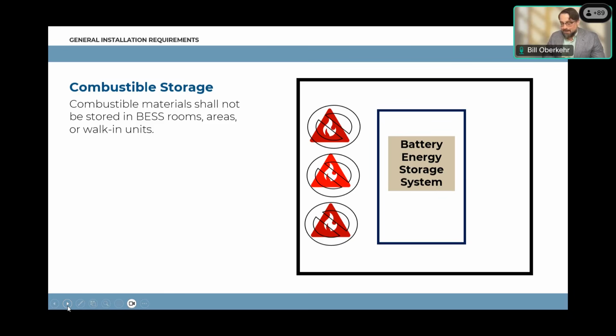And as Paul said, this is not a fire elimination code, it is a fire prevention code. To that end, the fire code requires that there be no combustible material within 3 feet of cabinets containing energy storage systems. This is critical, and it's one that unfortunately gets overlooked. It's one that NYSERDA's field inspectors look out for, and one required to be checked in those recurring inspections Paul talked about. Very important that no combustible material is stored within 3 feet of an energy storage system.